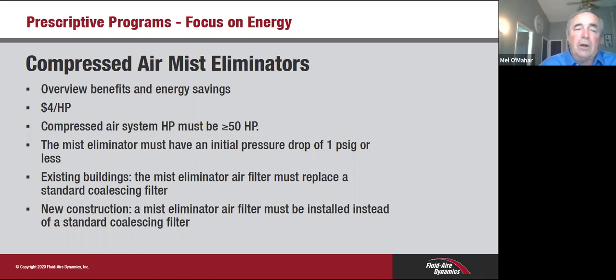So they are offering $4 per horsepower to install the mist eliminators. They're looking at systems that are larger than 50 horsepower. Mist eliminators must have an initial pressure drop of only 1 PSI or less. For existing buildings, the mist eliminator filter must replace a standard coalescer. So the whole theory behind this is to reduce pressure drop, and that's going to save you energy in the long run. Mist eliminators are good practice to put in lieu of a standard coalescing filter.